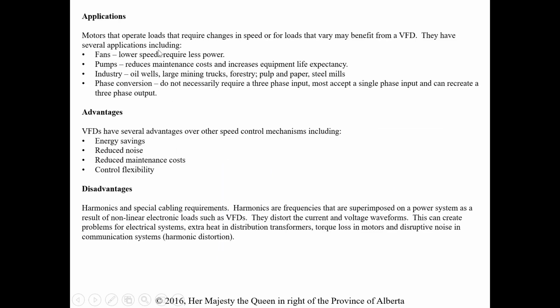Applications for VFDs that may benefit from the variable speed would be fans, pumps in industry, oil wells, large mining trucks, and phase conversion. So we don't necessarily require a three-phase input. Most accept a single-phase input and can recreate a three-phase output. So we talked about phase converters in third year, and those are kind of getting put to the wayside because we can use VFDs for phase conversion as well now. And they're becoming a lot cheaper than they were.